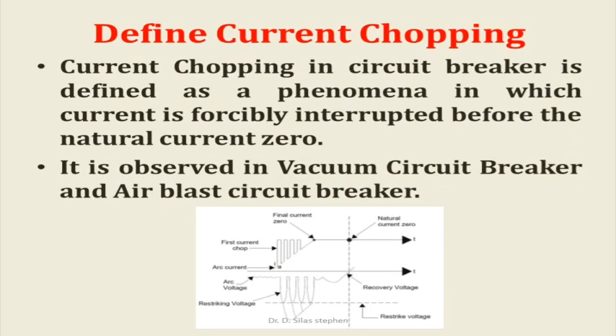Define Current Chopping. Current chopping in a circuit breaker is defined as a phenomenon in which current is forcibly interrupted before the natural current zero. It is observed in vacuum circuit breakers and air blast circuit breakers.